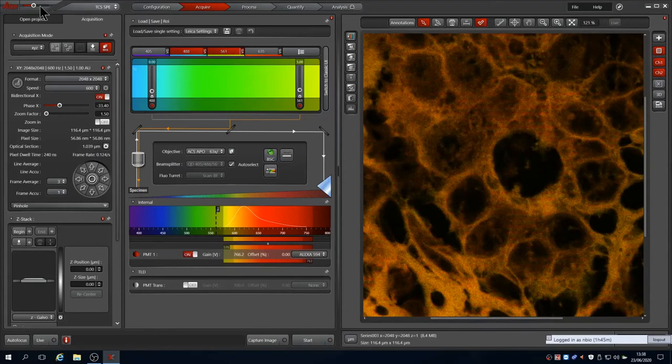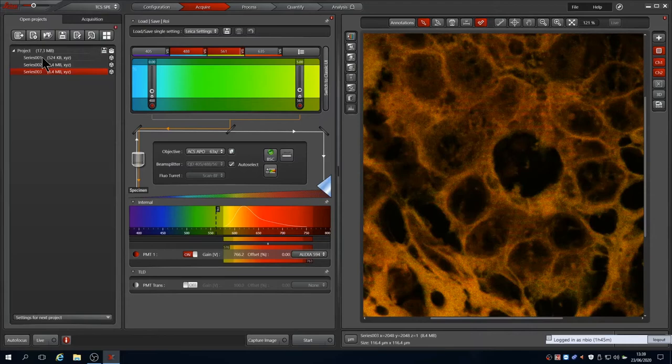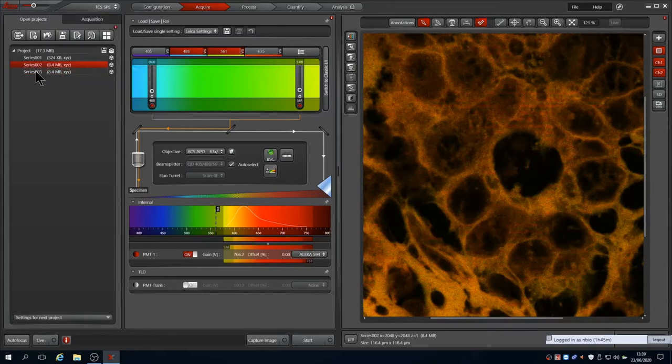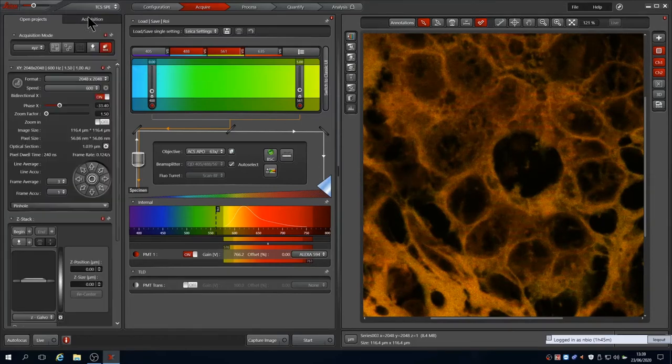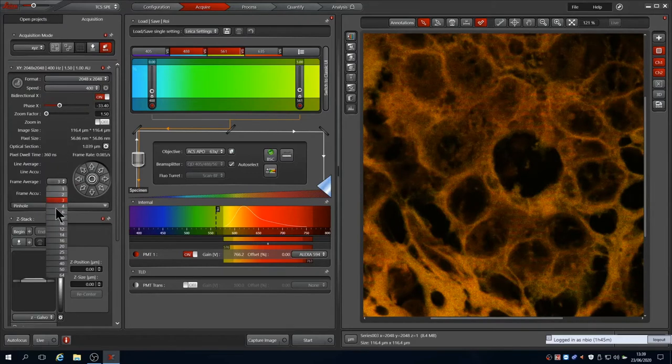Clicking on the tab for projects on the left, we can see the images we've taken. LASX is non-destructive and will keep all images captured except live images. If we compare series three with series two, it is evident we've improved the smoothness of the data. We can try improving further by slowing the scan speed down to allow longer integration of the PMT at each pixel, and further increasing the averaging.